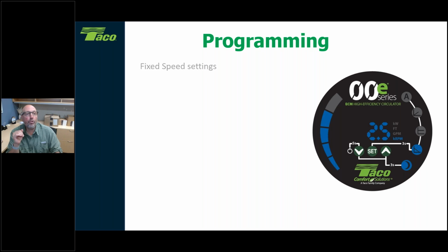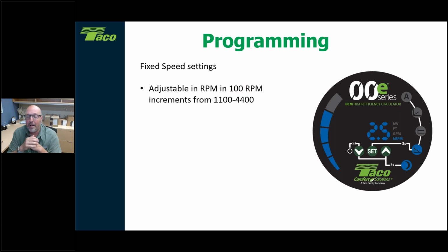So when you are programming the fixed speed setting, let's say we're in the fixed speed mode. To change the mode and get it out of the auto mode, you're going to hold down the set button for 3 seconds. Your speed here is going to be between 1100 and 4400. That's the range this circulator will work at. So the one light all the way down here starts at 1100, and 4400 is all the way up here. If I remember correctly, around 3800 RPM to 4400 was the 5th speed, and 1100 to around 1500 was the bottom light, and anywhere in between.